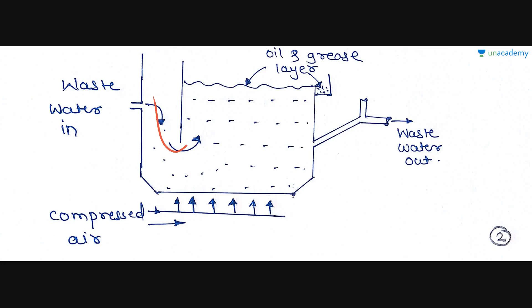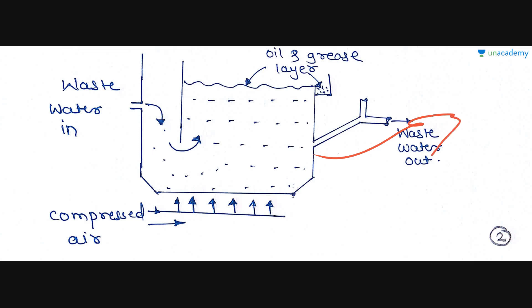In this section diagram you can see the Skimming Tank: wastewater enters from the top, compressed air is provided, and a layer of oil and grease forms at the surface. From a compartment, this oil and grease layer is removed and the wastewater is then sent to the sedimentation tank, free from oil and grease. Air is blown by an aerating device through the bottom; the rising air tends to coagulate or solidify the grease, causing it to rise to the surface where it is collected and removed.